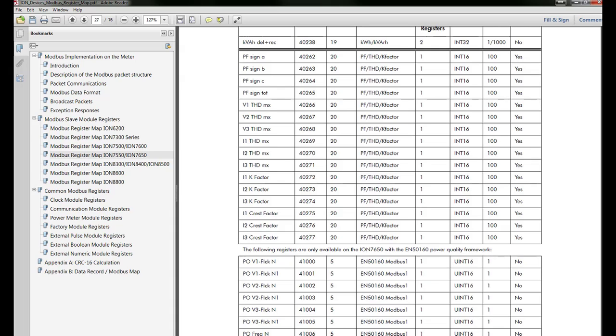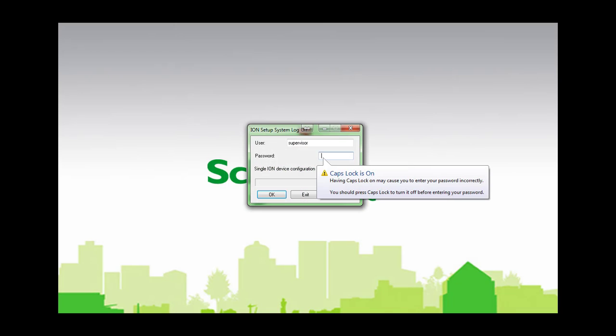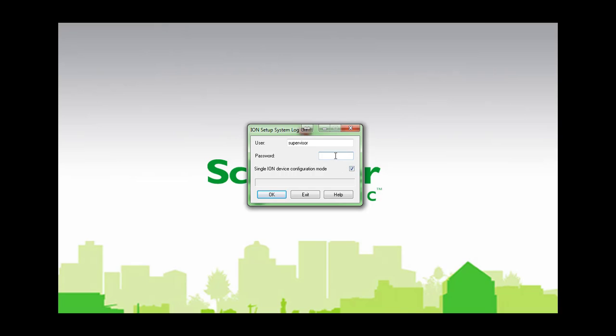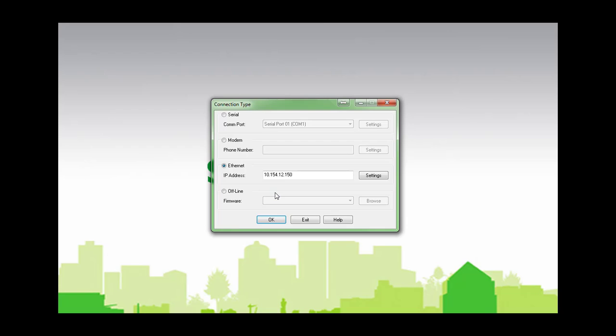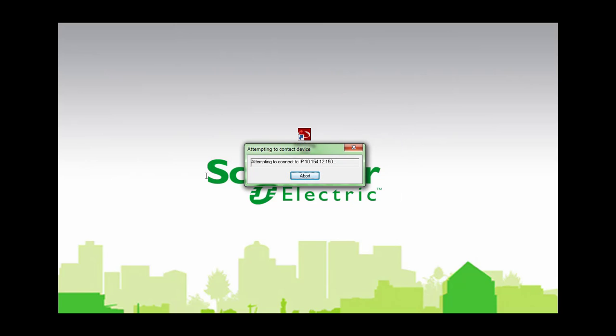So, what we need to do is connect to the meter with ION Setup, our configurator tool. First of all, type the password of ION Setup, which is 0, and then check the box in order to connect directly to the meter. Clicking OK, select the connection type, which usually is Ethernet, and then type the IP address. Just like this. Then we click OK, and we need to wait until we can contact the device.